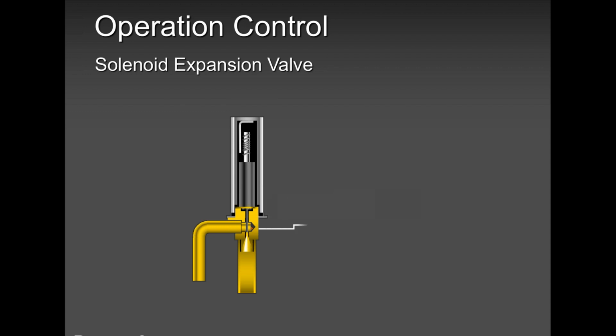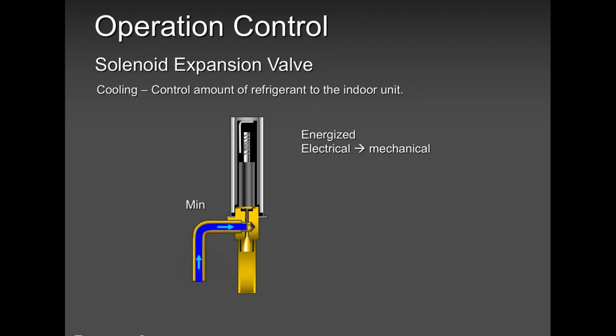Then we have the valve body, pipes, the valve chamber, the stopper. So please keep that all in mind, guys. Right now, there is hardly any call for cooling. Right now, we are in cool mode. It's hot, and the valve is slightly open. So you see the flow of refrigerant is very slow. That's when you have only 2 people in that room. You remember I showed you a slide with 2 guys? That's when you see this internally. You cannot see it when you're outside because everything is covered. But basically, this is how it looks when there is very little demand, when the heat load is not much.